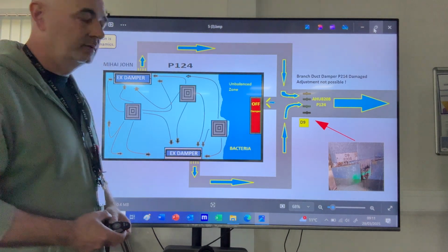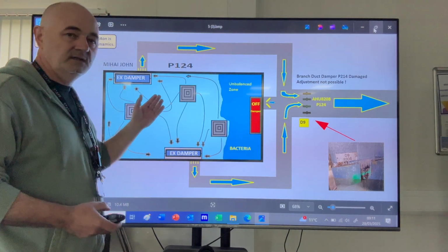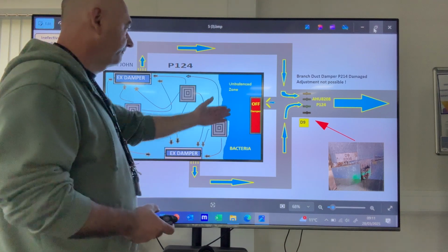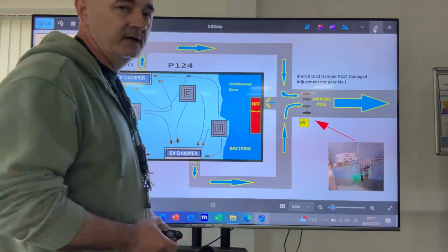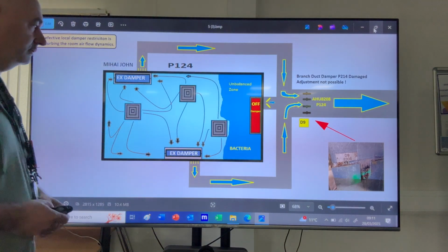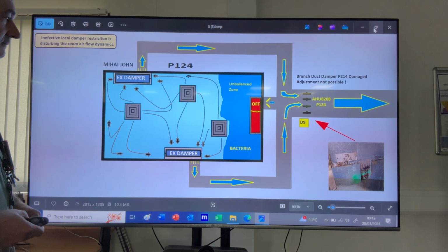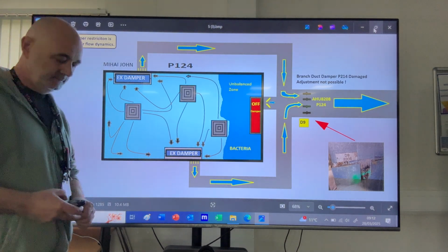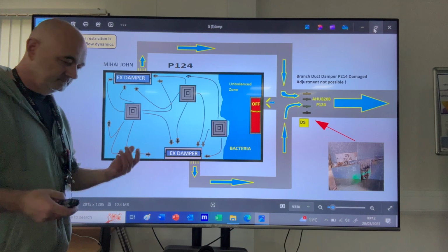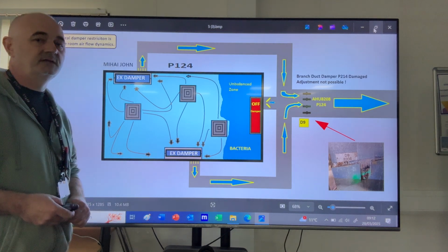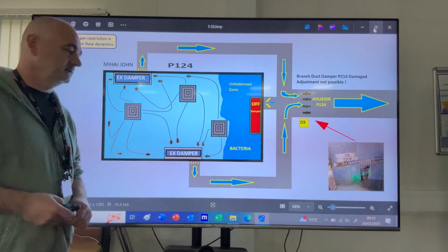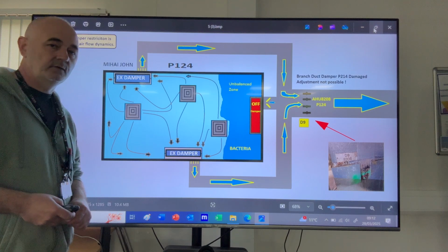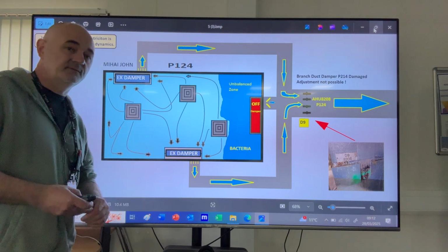Even if we have a global air change rate of 20 as it should be, this area is a dead area because we don't have the correct flow. That was an incorrect approach. I had a chat with my superior at the time, and I went through many conflicts because of this severe investigation I did.